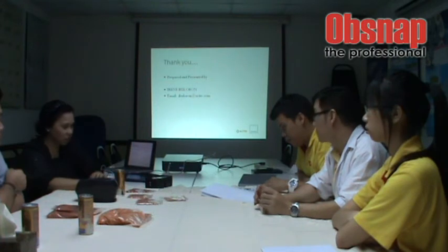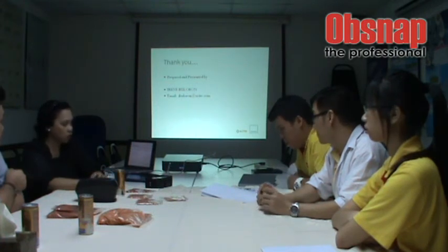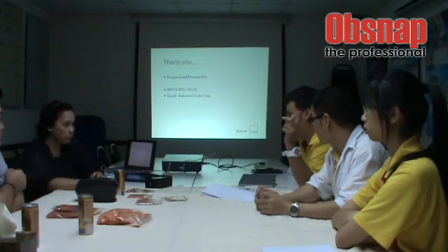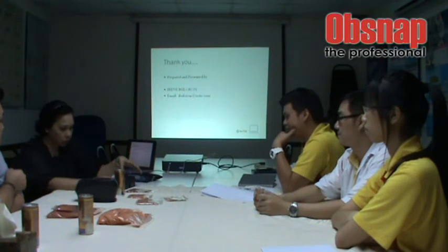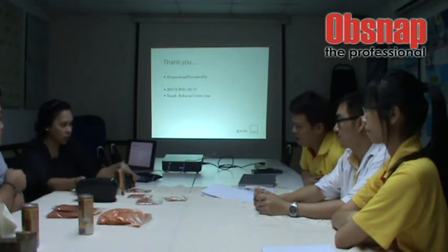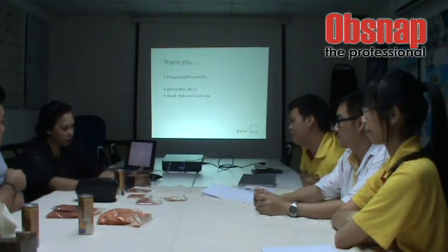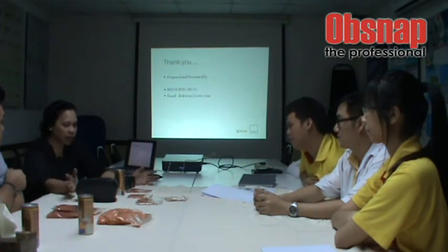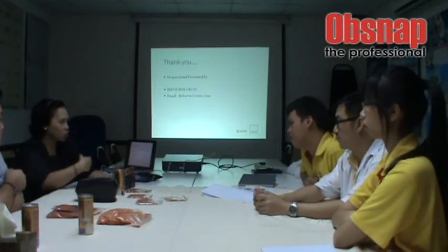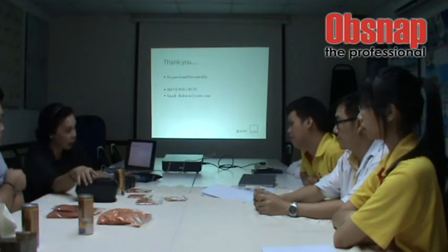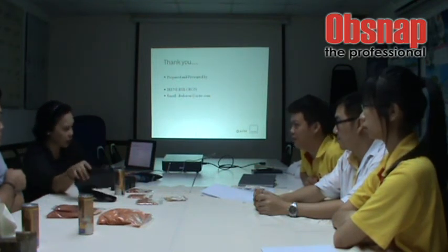Regarding the calibration issue, we need to send it for external calibration, or do internal verification. This can be done on a daily, weekly or yearly basis, depending on how you set the instrument. But on a yearly basis, normally, let's say you forgot to send this for calibration, don't let it stay for 3 years. Before 3 years, you need to send it to us for calibration again, because this has a lamp.